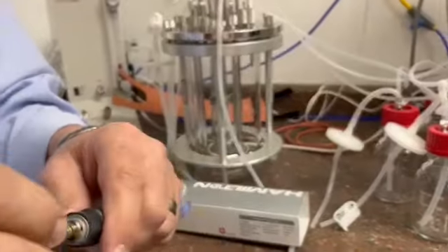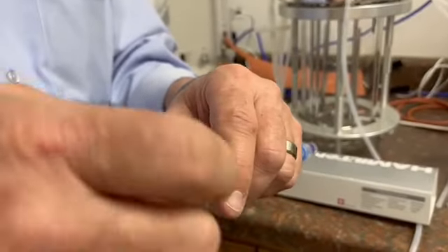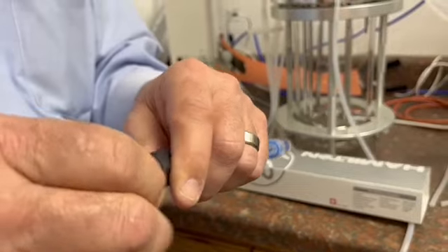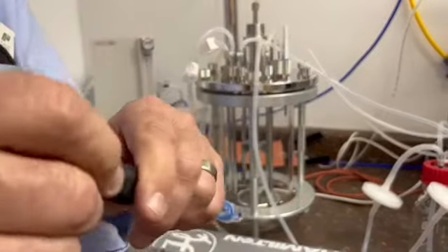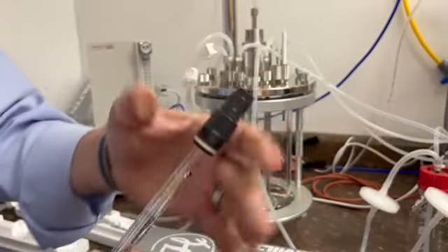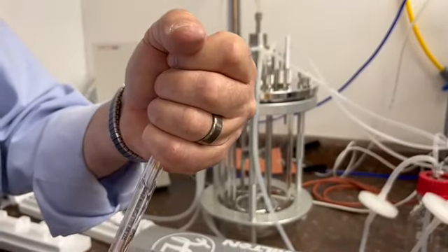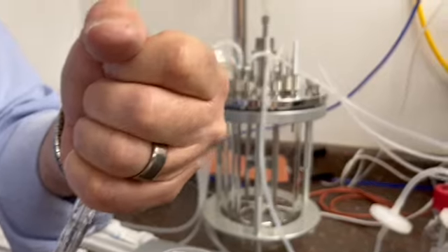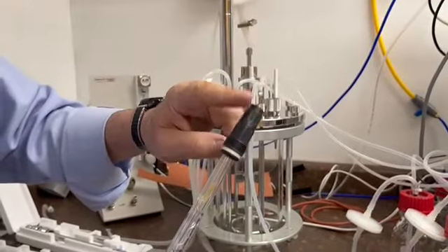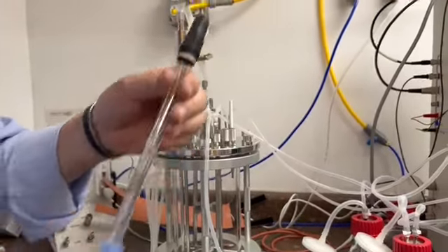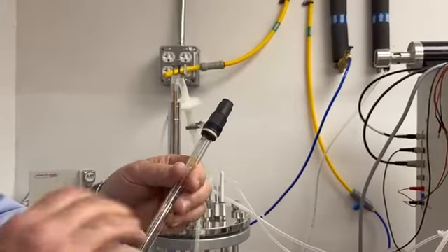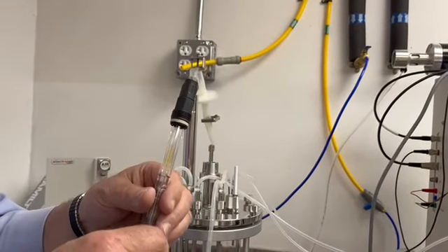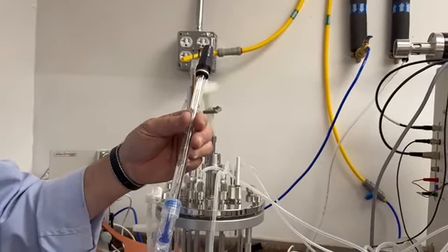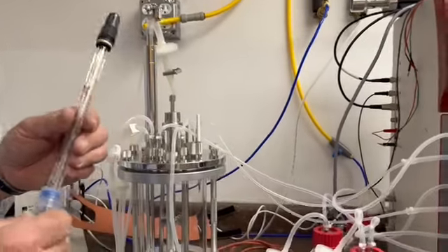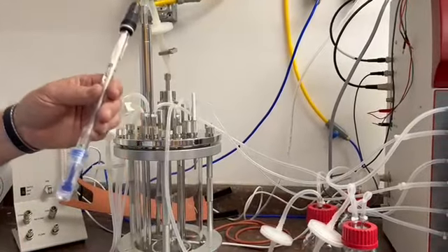Right? When you put this cap on, be gentle because these tend to crack in the autoclave. So you can feel there's a little seal in there. So just firm. Okay, I would still put foil over the top to give it an extra measure of protection. And actually, a lot of it is about protecting the cap. Yes. I mean, care of this is no different than any other pH probe you've got. They're all the same. It's got the glass membrane and all the rest of it. So it'd be the same thing.